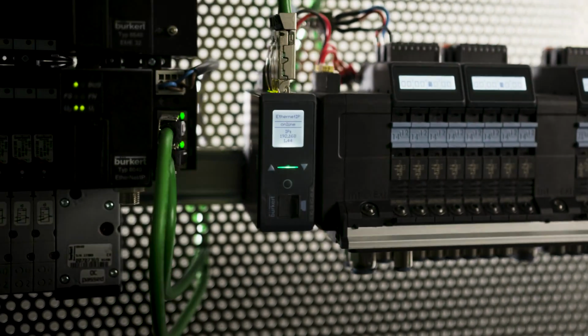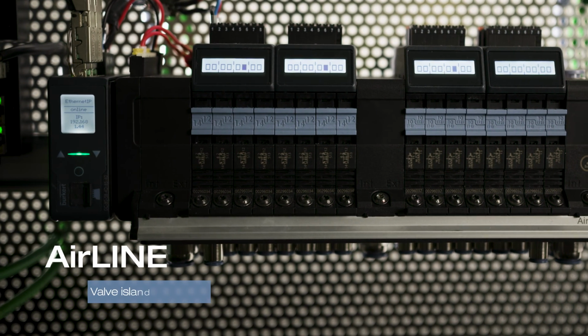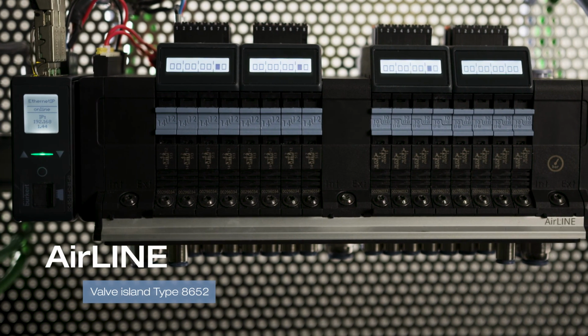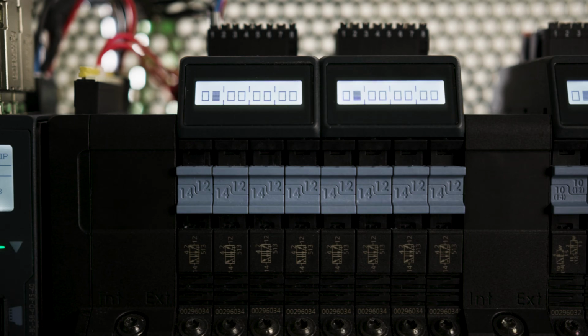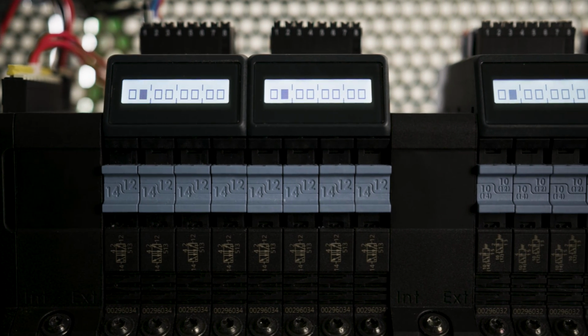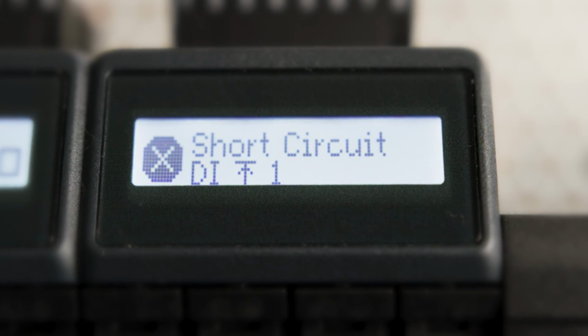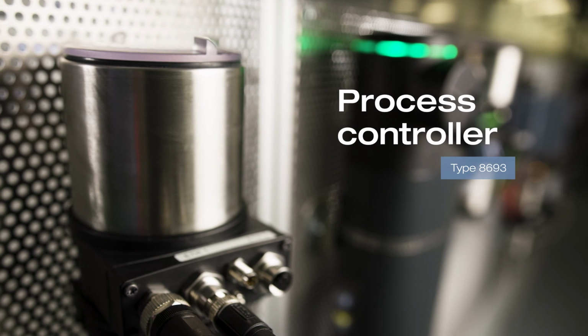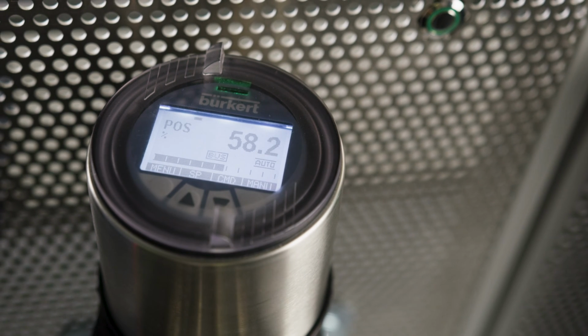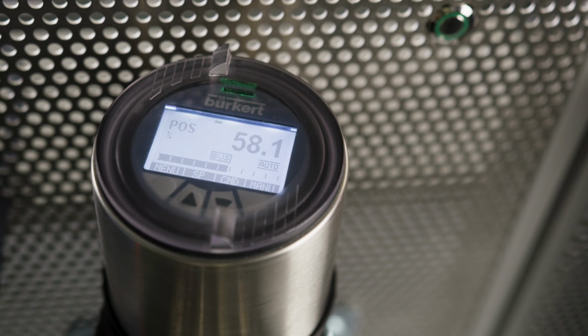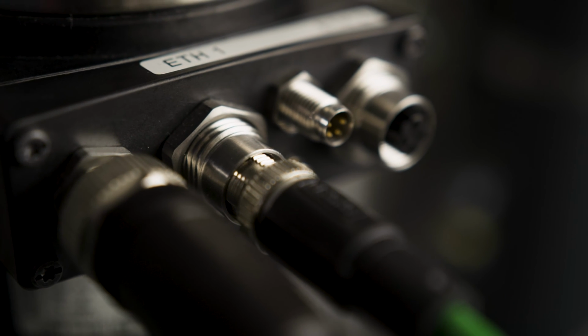One such device is the valve island type 8652, which has several valve units with integrated digital inputs. Each valve unit is equipped with a display to show valve switching states and some other diagnostic data. Another device in our setup is the process controller type 8693. In addition to the positioner functionality, you can also connect an analog sensor to it and use it as a controller. Add-on profiles save valuable time during commissioning.